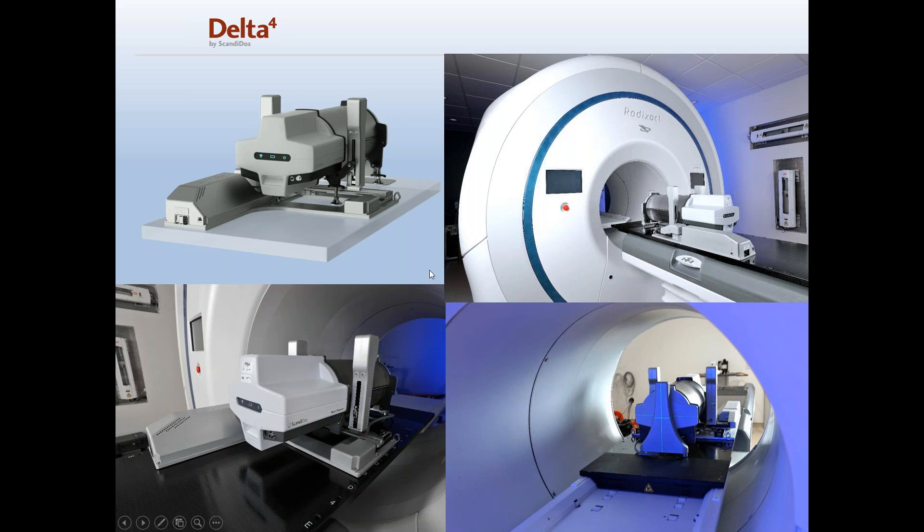Although this is being shown on Accuray's RadiXact system, it can be used on any LINAC, including things like Halcyon. It cannot be used in MR as the HexaMotion itself is not designed for MR. Although we make Phantoms for MR, the HexaMotion is not designed for MR motion studies.